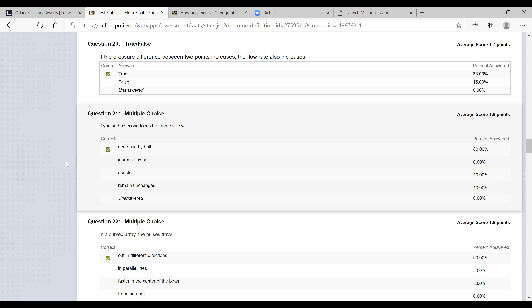All right. If you add a second focus, the frame rate will decrease by half. Some of you said double, some of you said remain unchanged. Well, remain unchanged is just wrong. Double's wrong as well. Frame rate is something we want, we want a high number. When we add a second focus, we take our high number and reduce it, pretty much by half. That's not good for our frame rate. It might be okay: if your frame rate was 100 and you reduce it to 50, that's still plenty of frame rate.